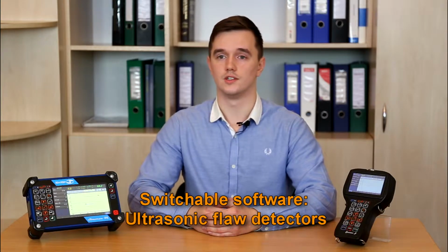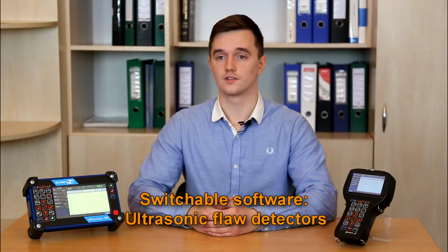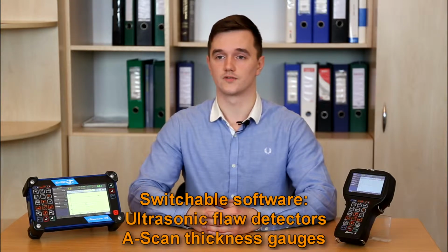As was already mentioned in my Sonocon product family review, these instruments are identical in their functions and differ mostly in their form factor and appearance. Both of them have two switchable software versions: UT, making them ultrasonic flaw detectors, and Thickness Gauge Plus, transforming them into A-scan thickness gauges with advanced corrosion mapping capabilities. In this video, I'll concentrate on interface basic concepts and will demonstrate them using the UT software version on the Sonocon B instrument.